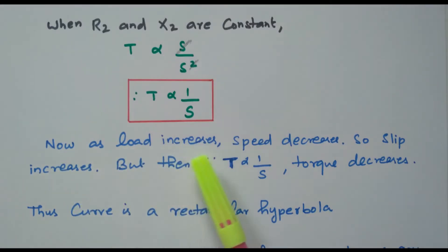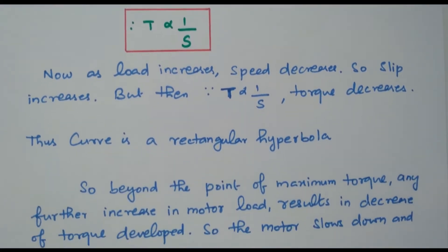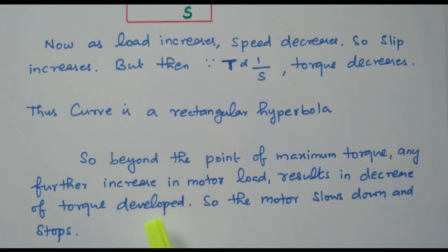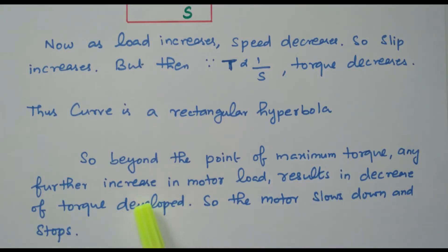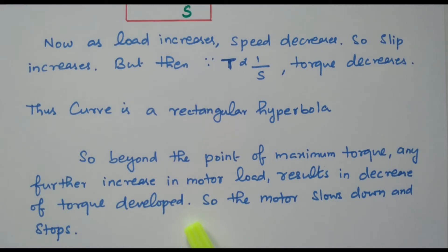As load increases, speed decreases and slip increases, but since T is directly proportional to 1/S, the torque decreases. This curve is a rectangular hyperbola (1/S). Beyond the maximum torque, any further increase in motor load results in a decrease of developed torque. So beyond the maximum point, if load is increased further, torque decreases, the motor speed slows down and the motor stops. We can load the induction motor only up to T_max at S equal to S_M.